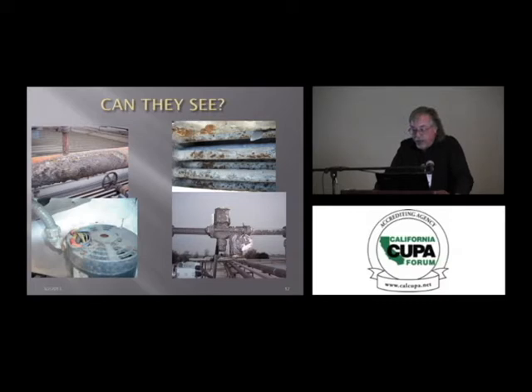And on the right-hand side, you'll see oil all over an ammonia valve, a solenoid valve and strainer. What is that oil telling you? Yeah, you've had a leak somewhere at one time, you're leaking now, or you're going to leak again. Lots of times the oil will come out first before the ammonia does. And it'll be nice enough sometimes to seal that gap up for us enough that we don't smell it. And then someday it's going to let loose.